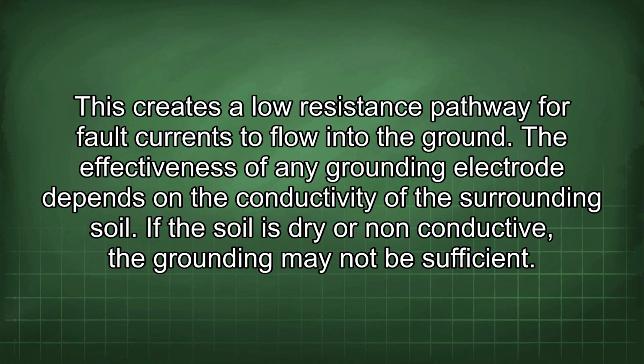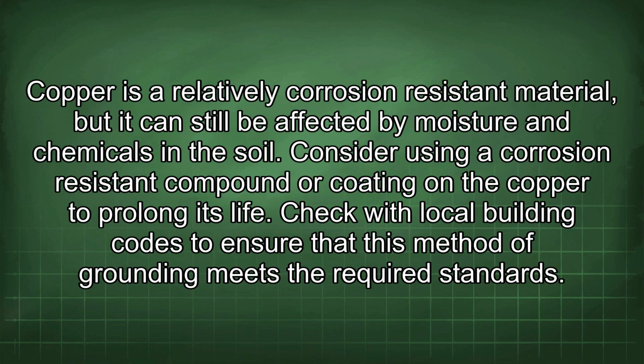The effectiveness of any grounding electrode depends on the conductivity of the surrounding soil. If the soil is dry or non-conductive, the grounding may not be sufficient. Copper is a relatively corrosion-resistant material, but it can still be affected by moisture and chemicals in the soil. Consider using a corrosion-resistant compound or coating on the copper to prolong its life. Check with local building codes to ensure that this method of grounding meets the required standards.